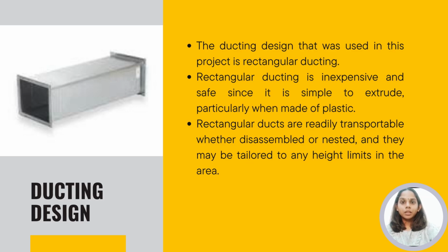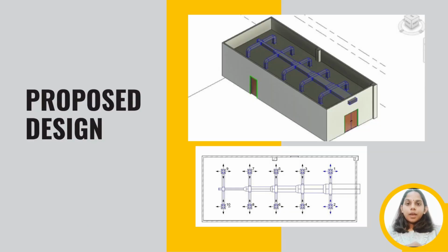Based on 2880 cfm, by using the ductilator, it will get a velocity of 1250 fpm, and the sizing for rectangular duct is 10 inches height and 40 inches width. For the better proposed duct, the air conditioner is increased in the value of cfm to avoid potential loss from any area of ducting. From 2880 cfm, it can be increased to 3050 cfm, with velocity of 1250 fpm, and the rectangular ducting size is 12 inches height and 42 inches width. And this is our proposed design of ducting in the office lobby. This ducting design consists of 10 branches.